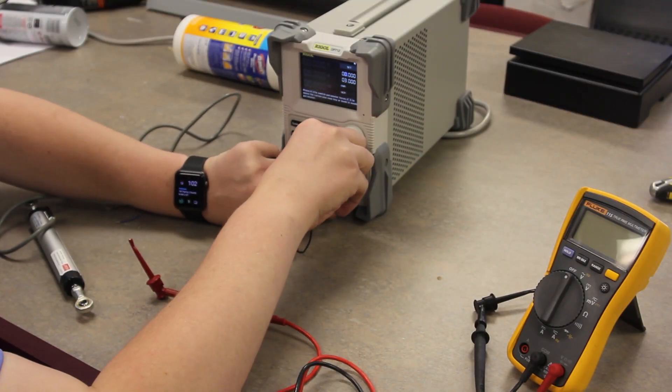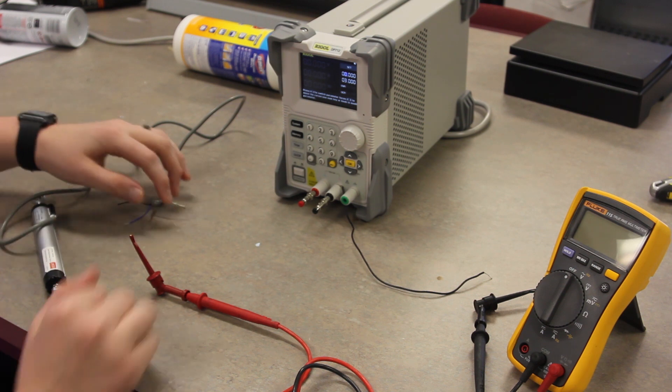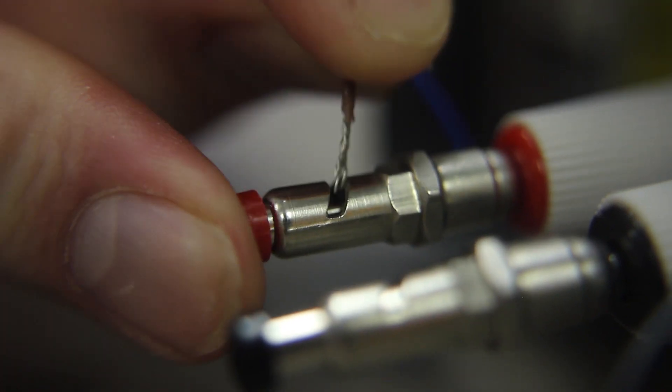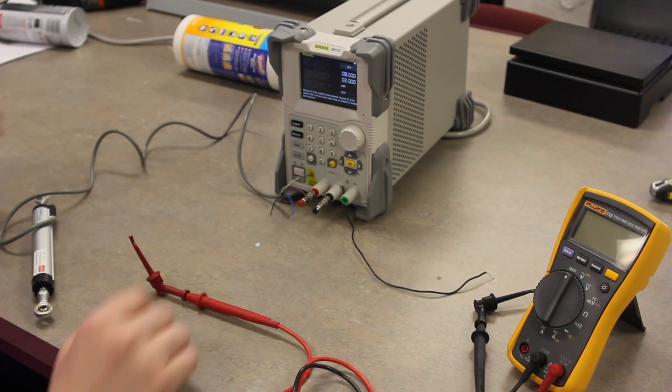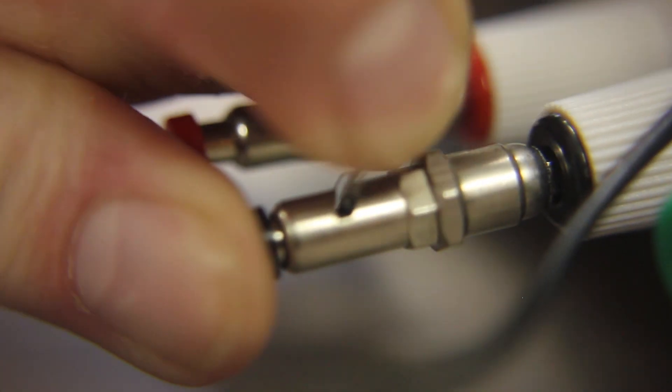Begin by attaching the jumper wire to the negative terminal of the power supply. Next, attach the sensor's positive excitation wire to the positive terminal of the power supply. Then, attach the sensor's negative excitation wire to the negative terminal of the power supply.